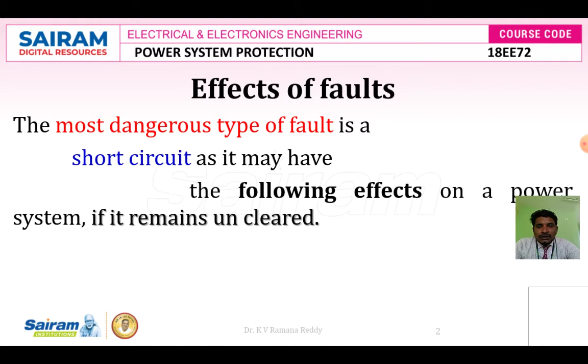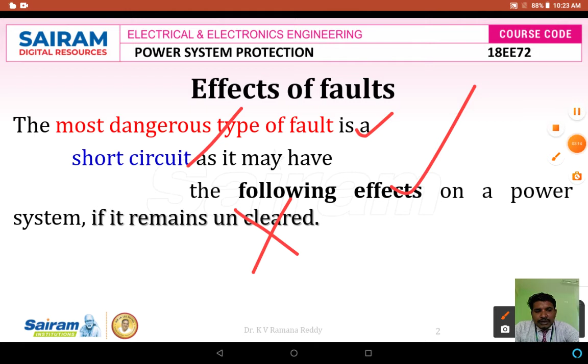Therefore, the most dangerous type of fault is called a short circuit fault, because it may have the following effects on a power system if it remains uncleared. If you do not clear that short circuit fault, then there is a chance of damage to the equipment. So let us discuss that. First of all, a heavy short circuit current may cause damage to the equipment, but also to other elements of the system. Damage does not only happen to the faulty element, but there is also a chance of damage to other elements of the system due to the overheating and high mechanical force set up by the heavy current.